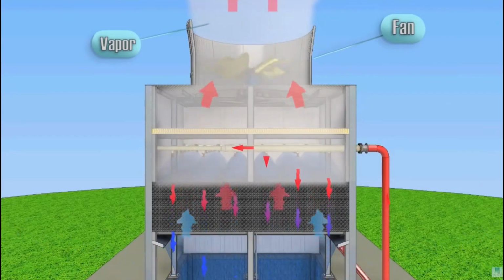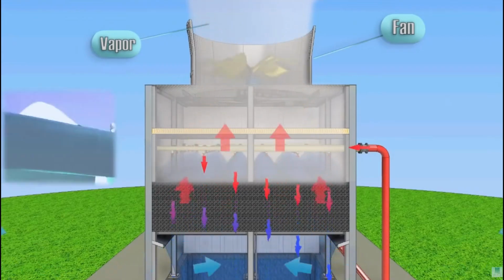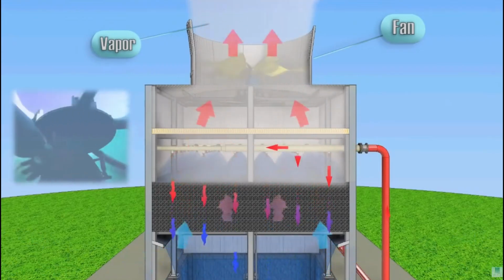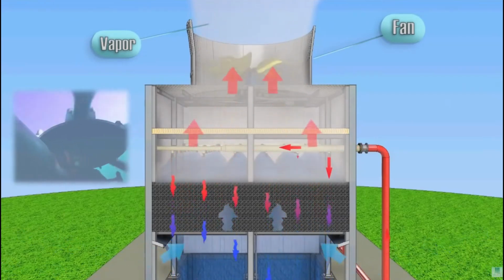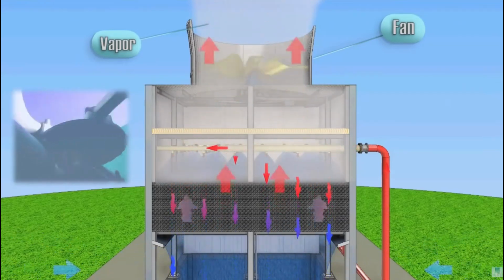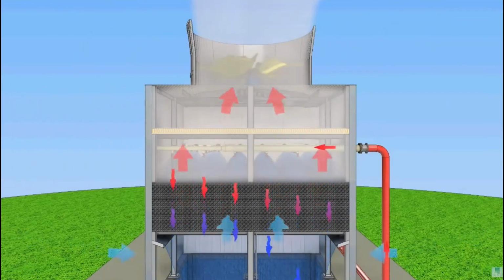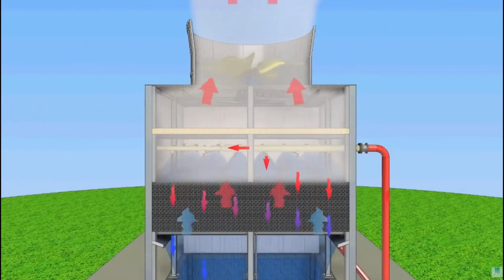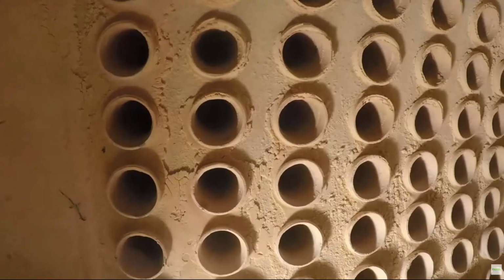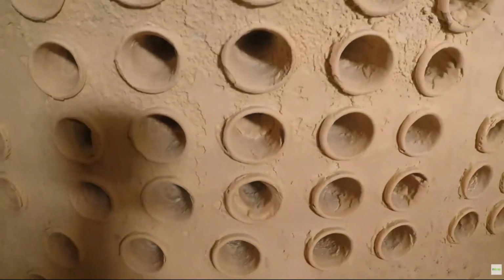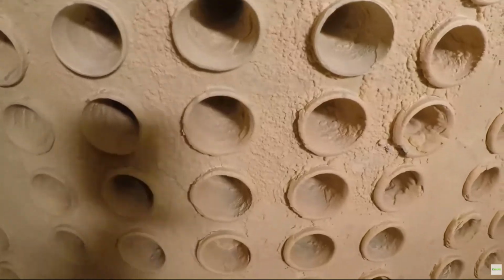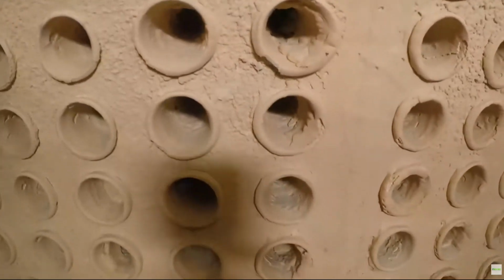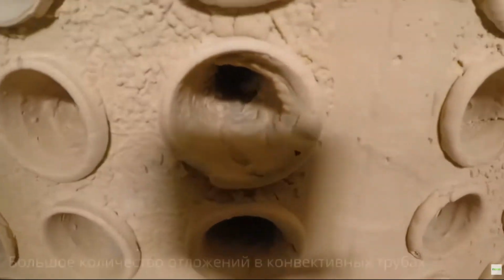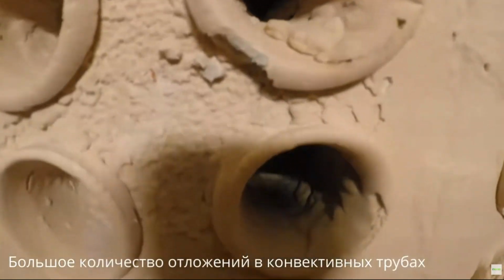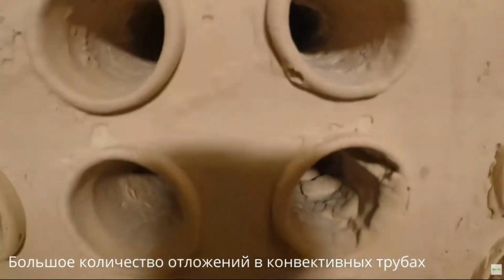The problem with evaporative cooling. Most research reactors today use wet cooling towers, evaporative systems. They're efficient, sure, but there's a problem. As water evaporates into steam, all the salts and minerals stay behind. These salts build up on the heat exchanger tubes between the first and second cooling loops.